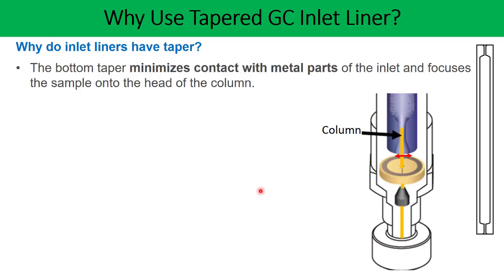The topic of today's discussion is: why do inlet liners have a taper? What is the purpose of using the taper in the liner? The first important point is that the bottom taper minimizes contact with the metal parts of the inlet and focuses the sample onto the head of the column. In the diagram you can see the column, and here is the taper near the cursor. Because of this taper, the sample is able to get focused onto the head of the column, and also minimizes contact with the metal parts. The size of the sample band gets narrowed because of this narrow taper.